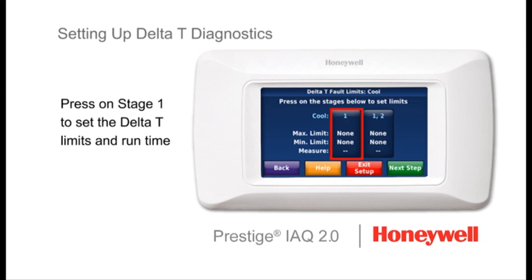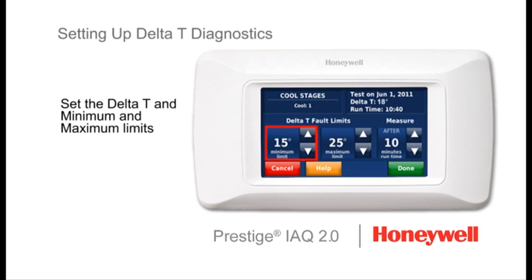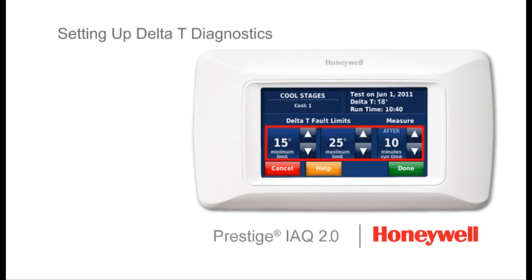Press on stage 1 to set the delta T limits and runtime. Set appropriate minimum and maximum delta T limit based on the delta T reading from the equipment test and what you consider to be unacceptable system performance. Select a runtime when delta T began to stabilize during the equipment test. When the thermostat is controlling the system, the thermostat will compare delta T to the minimum and maximum limits after the equipment has run for this length of time.